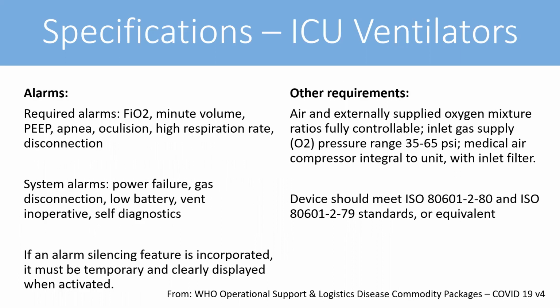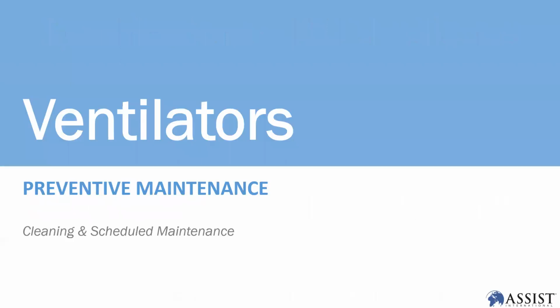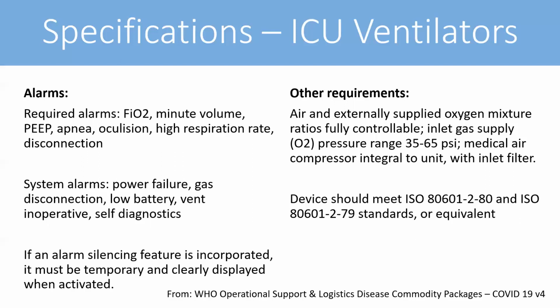So alarms are very important. I did mention that with these ventilators you have low alarm, high respiratory alarm, all that. Very important. Battery alarm, gas flow disconnection alarm, all this. It's very important actually. And the pressure line should be 35 to 65 PSI.